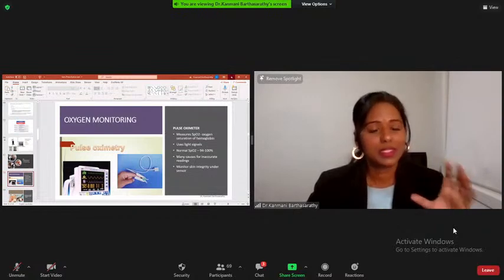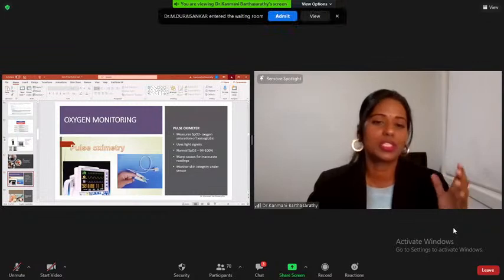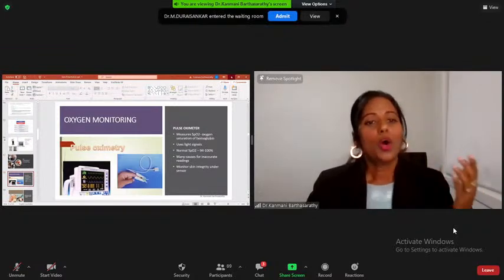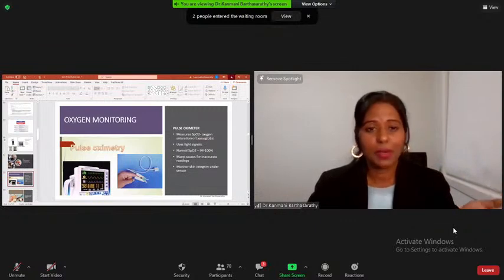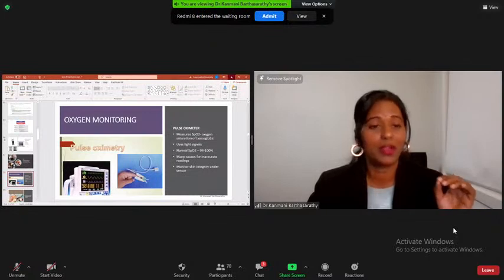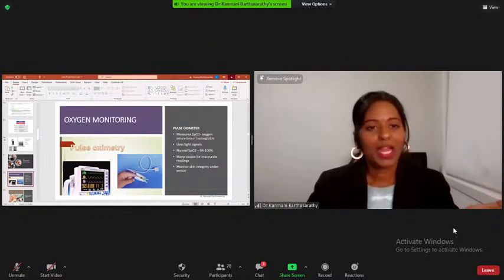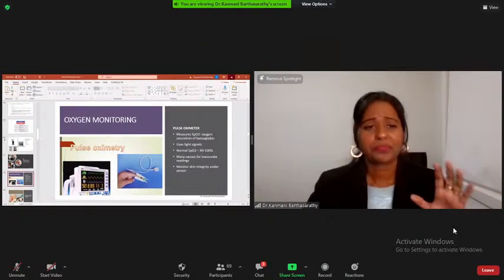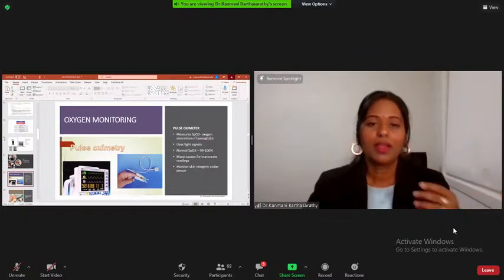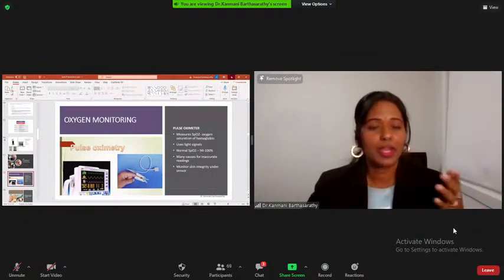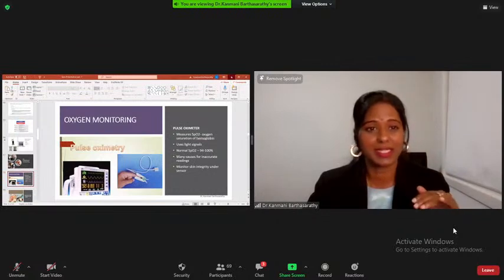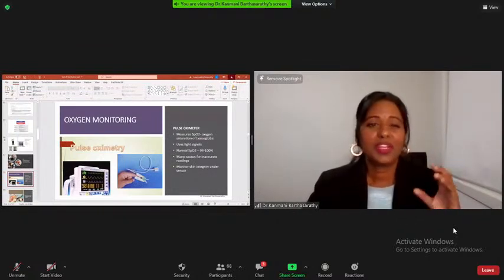This instrument uses light beams to estimate the oxygen saturation of the blood and the pulse rate. Oxygen saturation gives information about the amount of oxygen carried in the blood, by the red blood cells. Again, the normal value is 94 to 100%. They are reliable, accurate, and relatively inexpensive and portable. Pulse oximeters are often used for estimating heart rate at rest and during exercise. Hazards here are incorrect readings if the probe falls off the earlobe, toes or fingers, and skin irritation from adhesives on the probe.